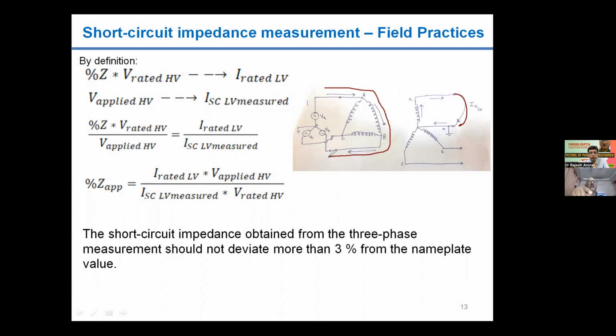So if you see from the formula, the percentage Z will be equal to I rated on the LV side multiplied by V applied on the HV side, divided by I short circuited, which we are measuring, multiplied by V rated. The detailed formula is given above. If you look into it, you will arrive at the final formula. Okay. So the short circuit impedance obtained from three-phase measurement should not deviate more than 3% of the nameplate value. Next.